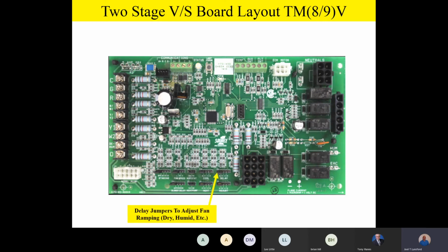Now, on the variable speed control board, we're going to have some jumpers that are really important that we look at our install information with, and to set these jumpers up properly for our airflow. Now, remember, team, we never set it up for your ductwork. So when you install these pieces of equipment, it's really important that you look at the install information and set them up according to your ductwork and the tonnage of the outdoor unit. One more time, 400 CFM per ton is where we want our cooling airflow. 400 CFM per ton for our high cooling airflow on our products.